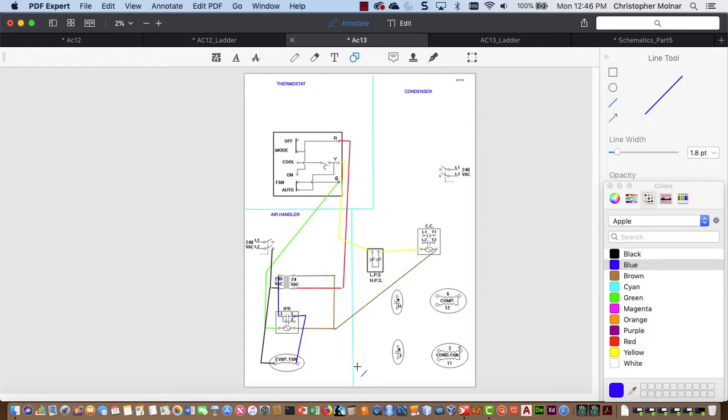Okay, see anything I missed on the line voltage side? Not really. I'm not entirely happy with how close that is, so let's go ahead and pull this and just make a connection. I want to show very clearly that's two separate wires. Okay, now let's take a look at my condenser side. Again, I'm going to use, we didn't connect that in. Might help if we give it some power. So let's go ahead and give some power here. Sometimes easy to miss a terminal. Got to go back and double check everything, just as you do in the field.